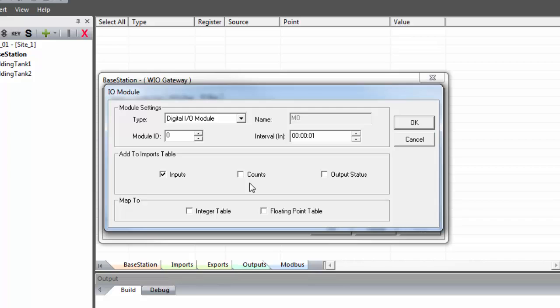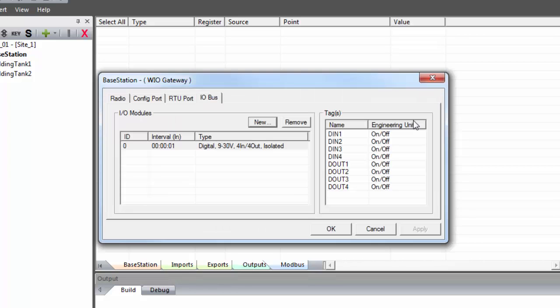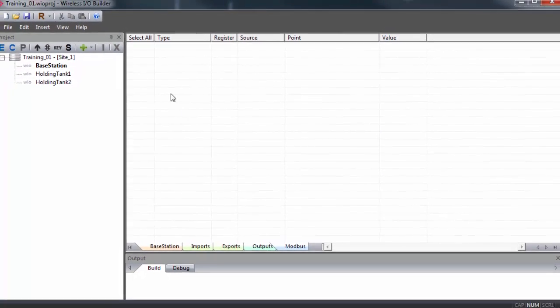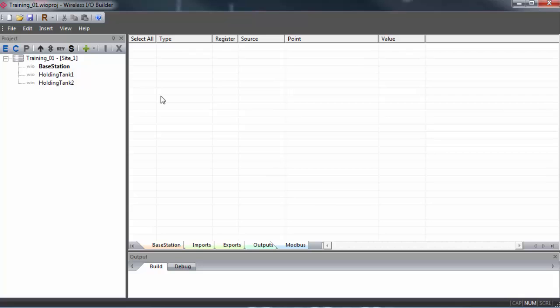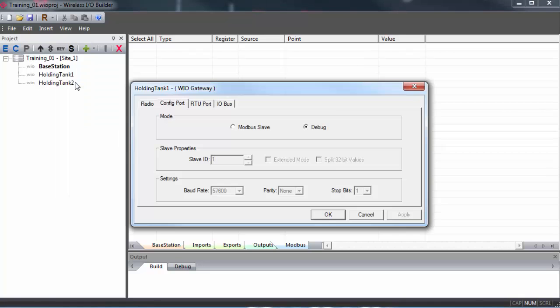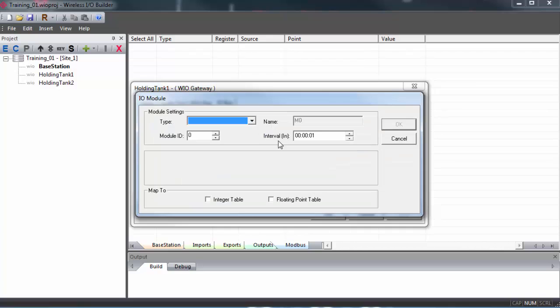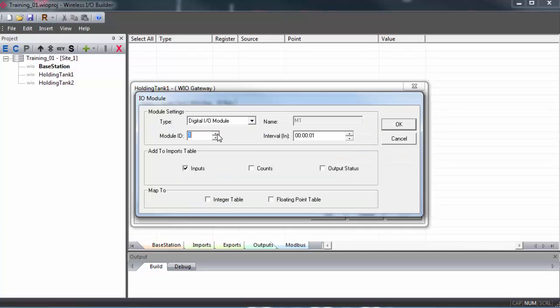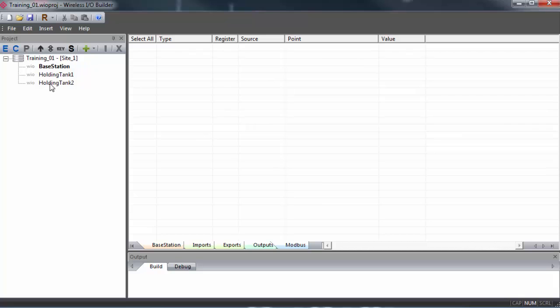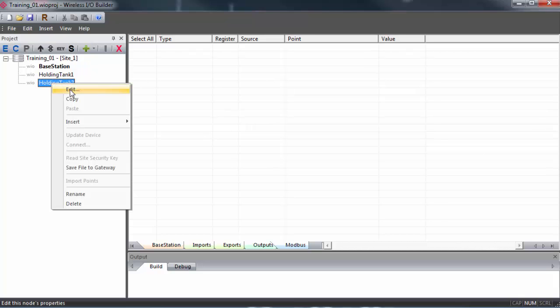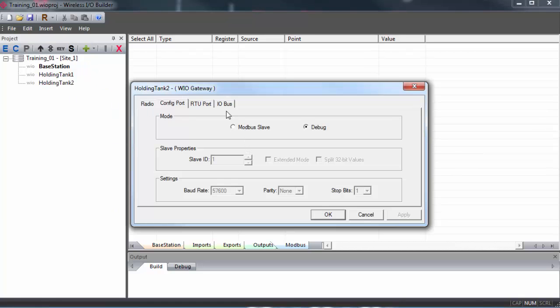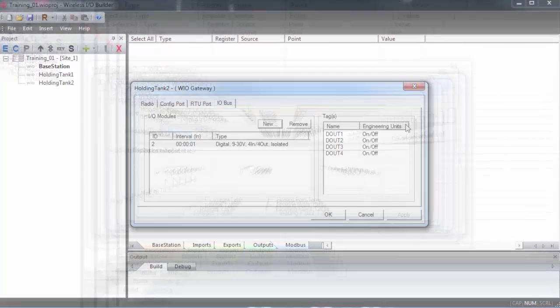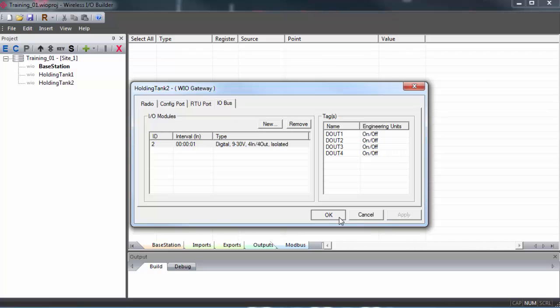So if you need to set the dial on an IO module to a different ID, you'll have to power down the group, set the dials, and then power back on. We can see the module name here. It's just derived from the ID number. We can set the interval. Lowest setting is one second. And we can choose what to bring into the imports table. This only applies to the digital module type. You'll see the difference from the analog IO modules in a little bit. To begin, I'm just going to add the inputs.